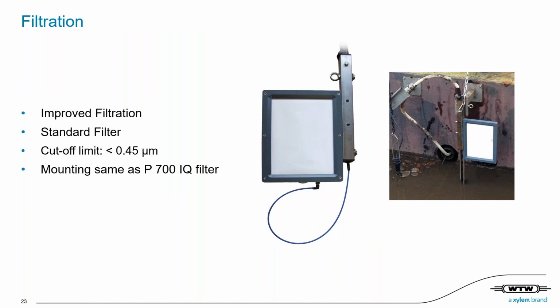Thus, we also improved our passive filter for the Alyza units. The filter material itself is more robust, and the material between the two filters is more rigid, making it really easy to periodically clean. Thanks to the installation on a rail, it can be easily removed out of the process for maintenance. In addition, it has a larger surface area, so will require less frequent cleaning. Last but not least, the expected life of the filter is greater than 1 year. From our experience, even 2 to 3 years, without exchanging the filter material.